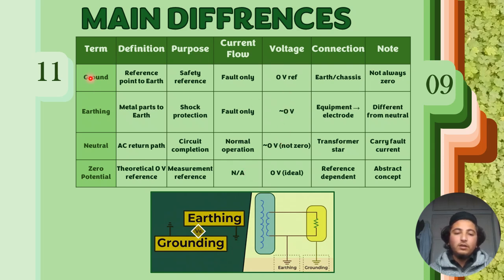Voltage difference in these four: grounding is at reference, so 0 volts; earthing is sometimes near 0 volts; neutral is near 0 volts but not exactly 0 because some charge remains; and zero potential is 0 in the ideal theoretical case. Connection-wise: ground is connected to earth or chassis and earth equipment electrode, neutral is connected to the transformer star point as an example of a neutral wire, and zero potential is reference dependent.